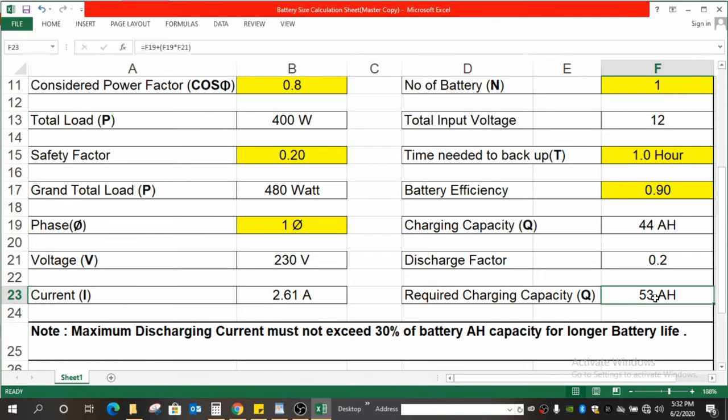Then the next part is how to select the battery. First question arises: is a 53 Ah battery as per our custom requirement available in the market? Mostly it's not. If it is not, then what to do? What is the next available size? If it is 55 Ah or 50 Ah, what is the next size? It may be low, it may be high. So as per that, we have to select the battery size.